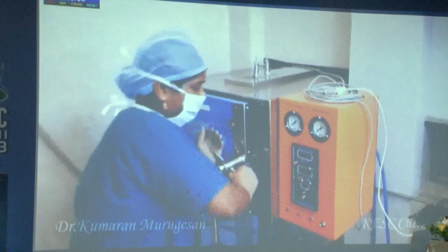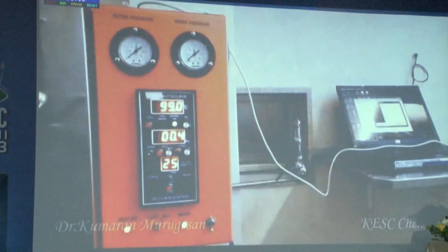We have a horizontal autoclave. The advantage of a horizontal double door autoclave is that one end opens into the CSSD area, the other opens into a sterile area. So you need not take all your instruments from an unsterile to a sterile area again. The parameters, there are 2 parameters, 121 degrees Celsius, and another one is 134, which is used for the flash sterilization process, but not to be used as a routine sterilization. This is a troubleshoot for your Helix test. Based on the color change, you can see what has gone wrong. So if you're using porous loads, use the Bowie-Dick, or a hollow instrument and both porous, use the Helix PCD test.